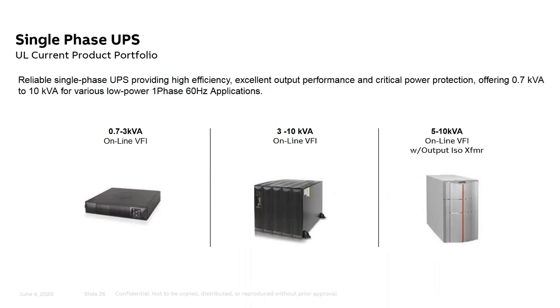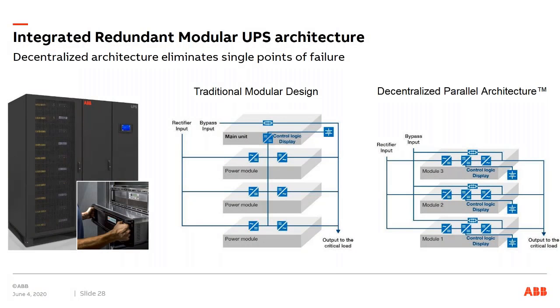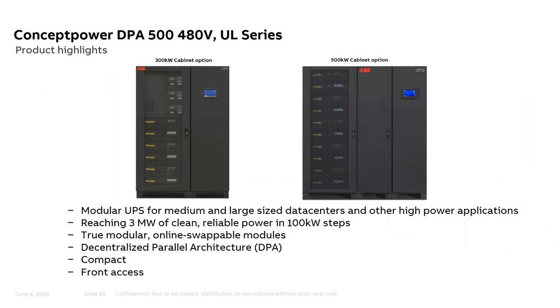So I should mention, I'm not going to talk an awful lot about that, but we have a line of smaller single phase UPSs, and of course technically they are monolithic. They're not typically what we would consider in a data center environment. So the other side is the modular scalable type products, and I'll just quickly go through a couple. There's a 480 volt line of the modular scalable products. At the 480 volt level, there are two different frame sizes. They're both based on the same power module, which we can actually see on the left side of the cabinets.